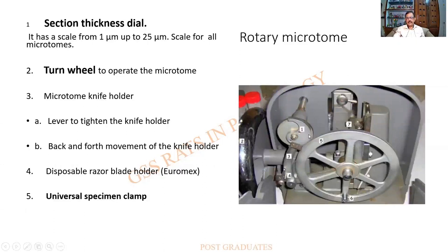On the inside, there is an adjustment for varying thickness, and the back side of the tissue holder shows that once movement occurs it moves a wheel which pushes the block holder forward — that is the basic mechanism. There is a turn wheel for fine adjustment, and on the other side the coarse adjustment. Not very simple, but not very complex either.